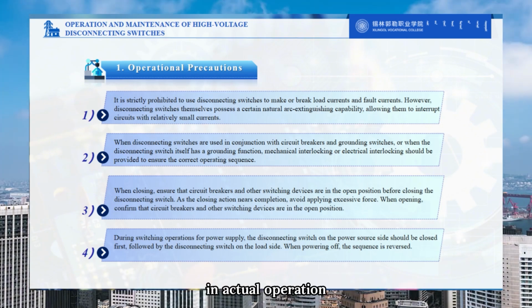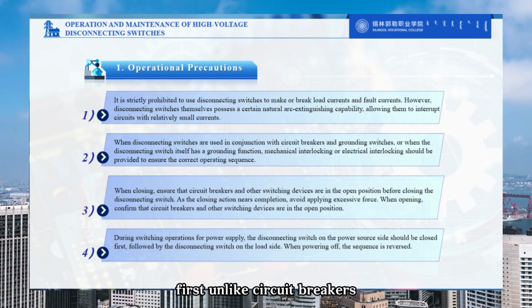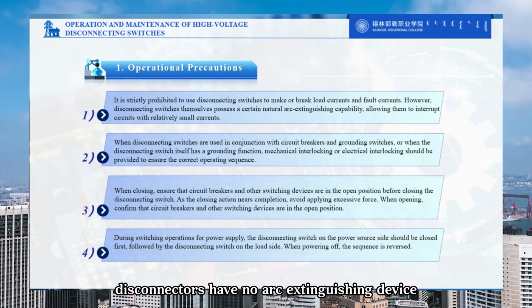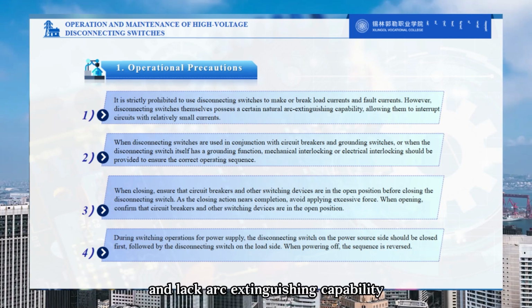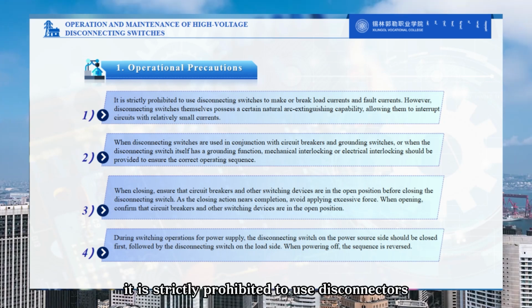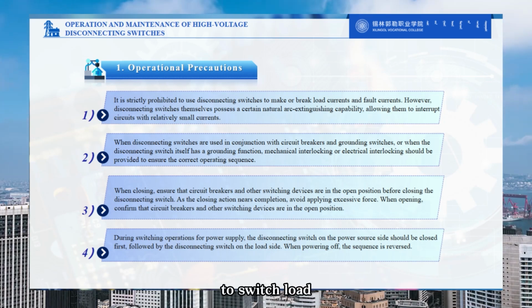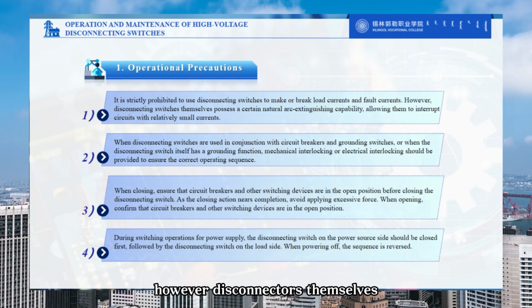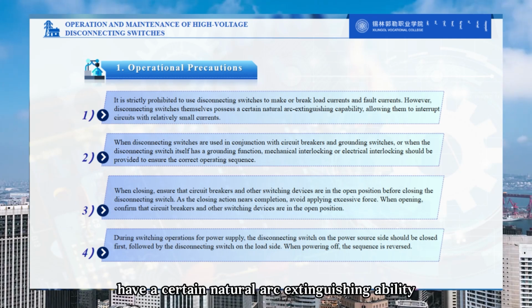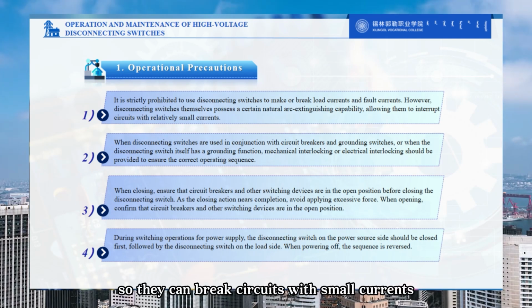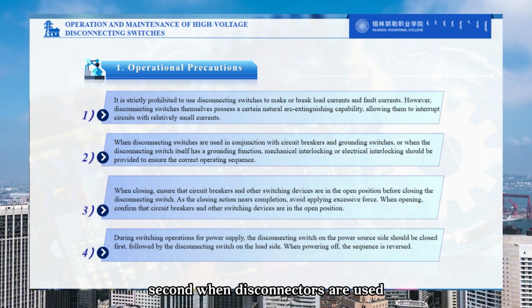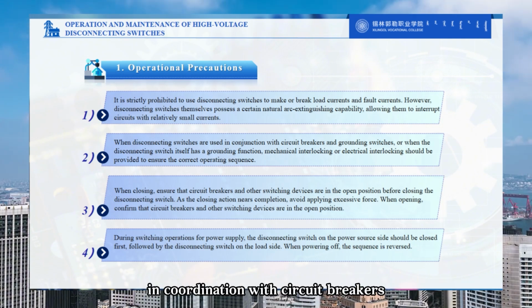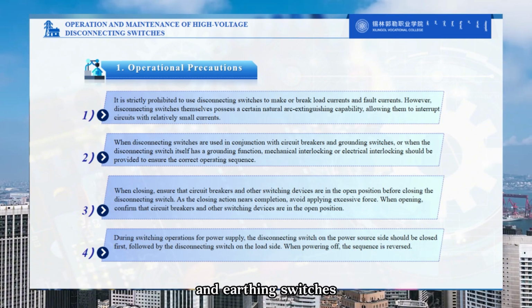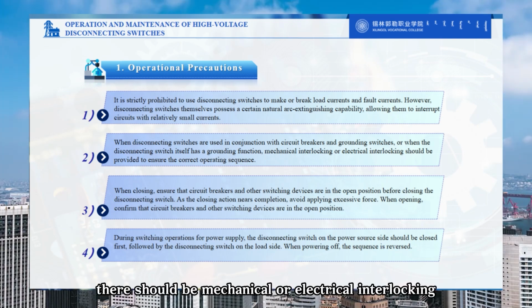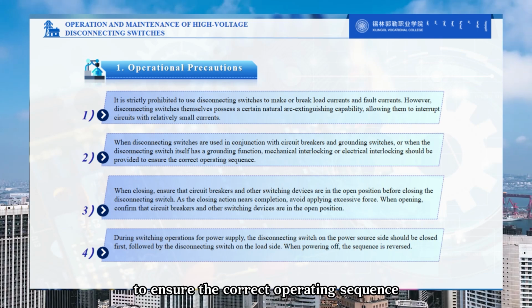In actual operation, the following points should be noted. First, unlike circuit breakers, disconnectors have no arc extinguishing device and lack arc extinguishing capability. Therefore, it is strictly prohibited to use disconnectors to switch load current or fault current. However, disconnectors themselves have a certain natural arc extinguishing ability, so they can break circuits with small currents. Second, when disconnectors are used in coordination with circuit breakers and earthing switches, or when the disconnector itself has an earthing function, there should be mechanical or electrical interlocking to ensure the correct operating sequence.